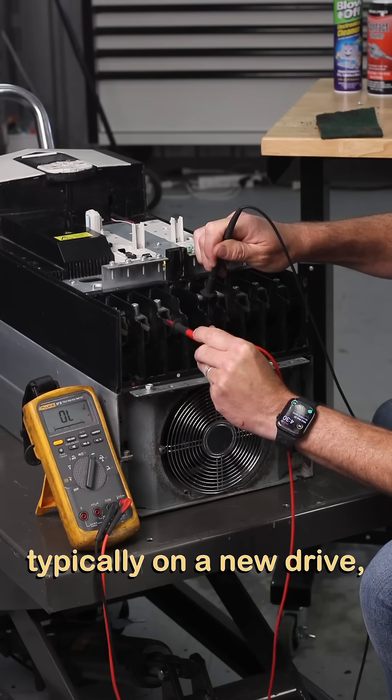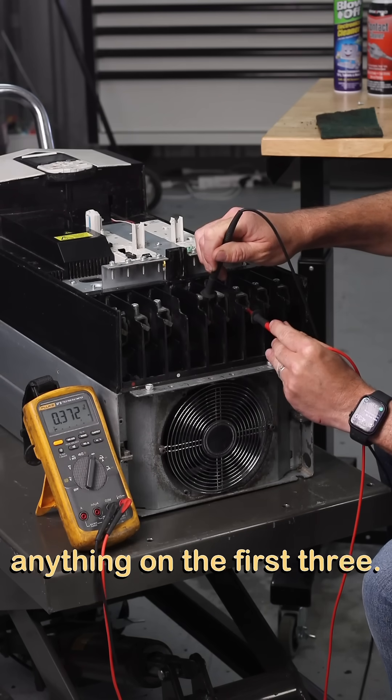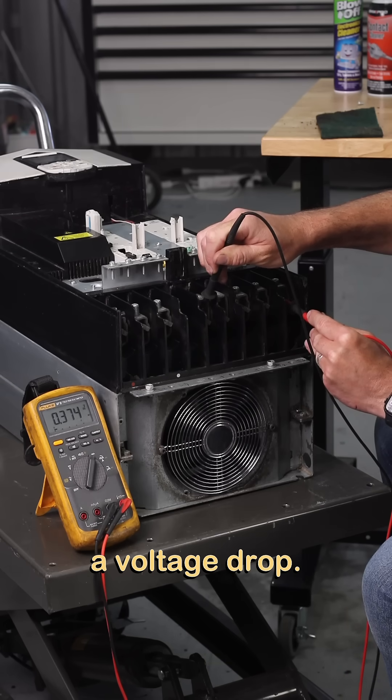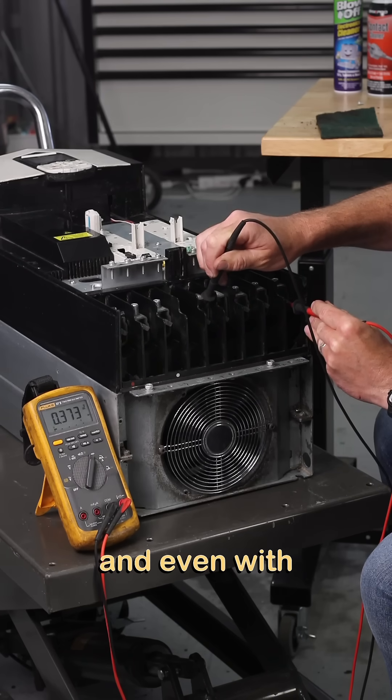On a new drive, we're going to see a precharge circuit, and it doesn't actually do anything on the first three. Whenever we go to the outputs, we'll hear a good solid single beep, and that will indicate a voltage drop. We want to see it nice and stable, solid, and even with the others.